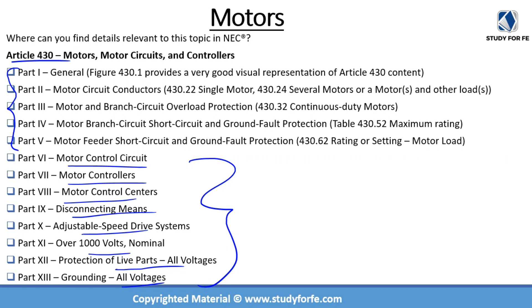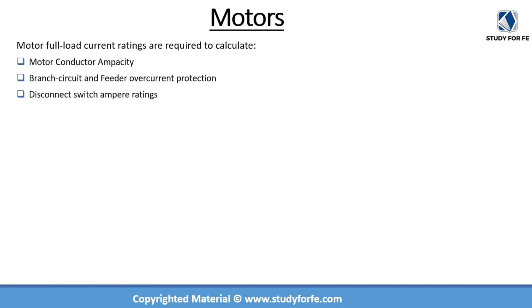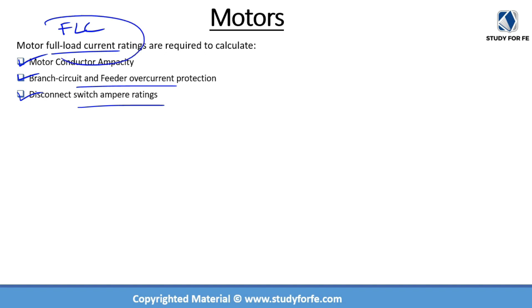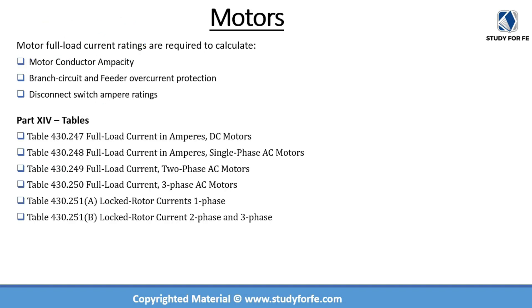The first five parts are very important because they are focused on motors. As mentioned earlier, motor FLC shows up again and again because the code requires us to use FLC for motor conductor ampacity, conductor sizing, branch circuit and feeder circuit overcurrent protection, overload protection, disconnect switch ampere ratings, and so on. So the question is: where do you get this data? Where do you find the motor full load current? So far we've discussed the first five parts of Article 430 in relative detail.